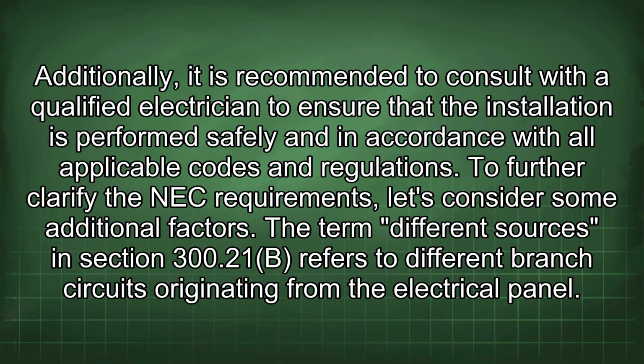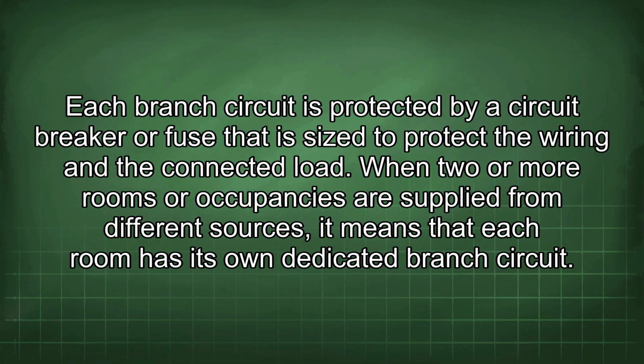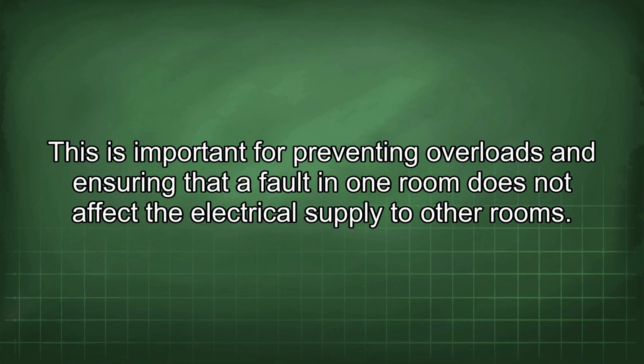To further clarify the NEC requirements, let's consider some additional factors. The term different sources in section 300.21(B) refers to different branch circuits originating from the electrical panel. Each branch circuit is protected by a circuit breaker or fuse that is sized to protect the wiring and the connected load. When two or more rooms or occupancies are supplied from different sources, it means that each room has its own dedicated branch circuit. This is important for preventing overloads and ensuring that a fault in one room does not affect the electrical supply to other rooms.